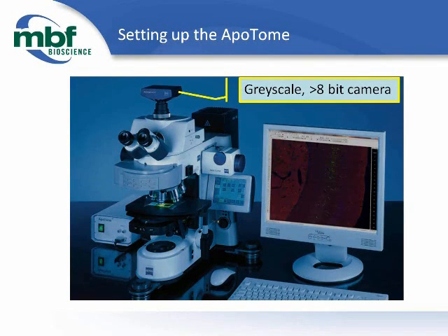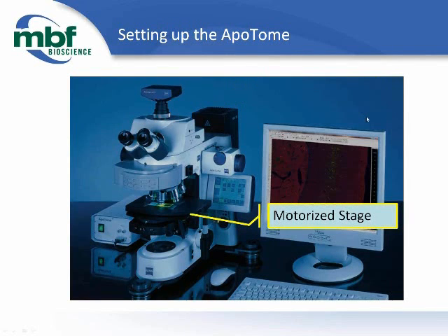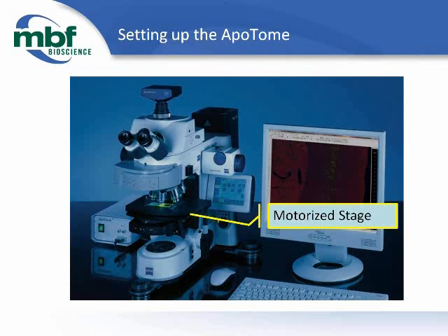A high-bit depth digital camera is required for structured illumination, as the extra dynamic range is particularly important. We will be removing a significant amount of out-of-focus light from the scenes you will be imaging. Additionally, you will need a motorized stage. This allows you to take advantage of the sophisticated software tools available in Stereo Investigator and Neurolucida for navigating and analyzing your tissue samples.